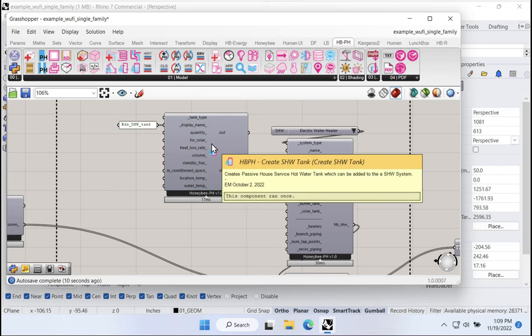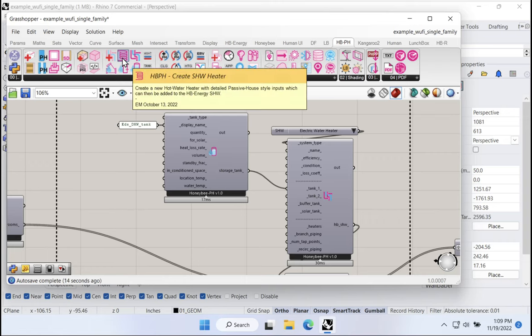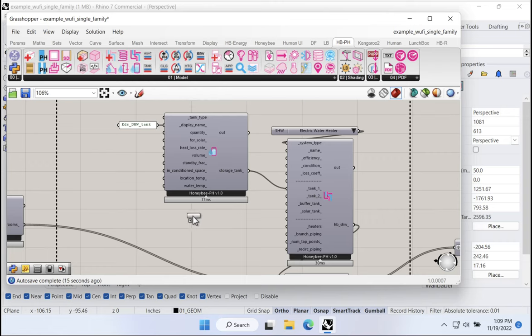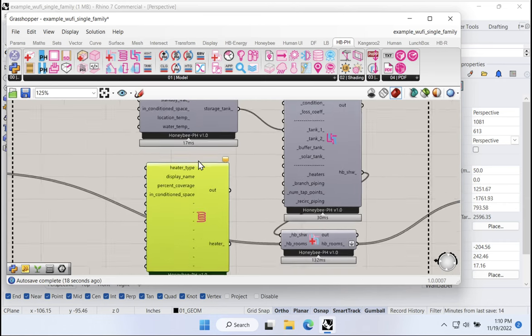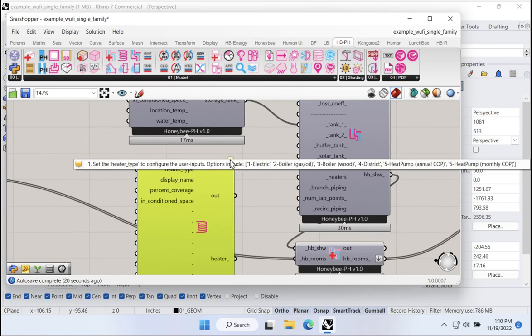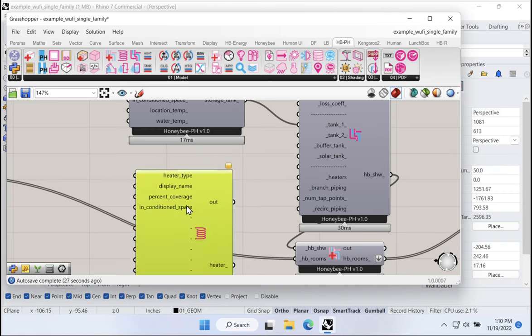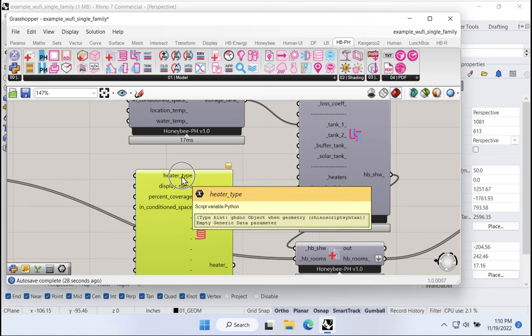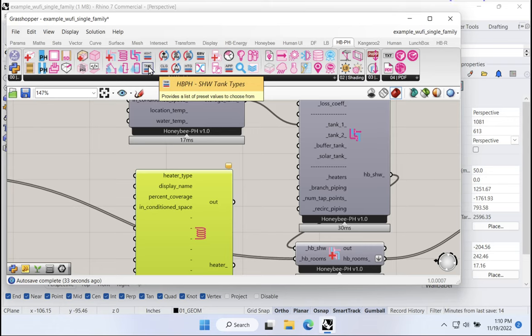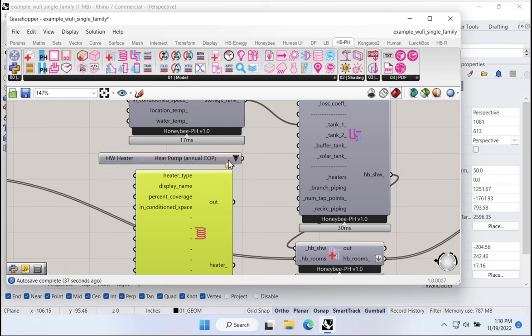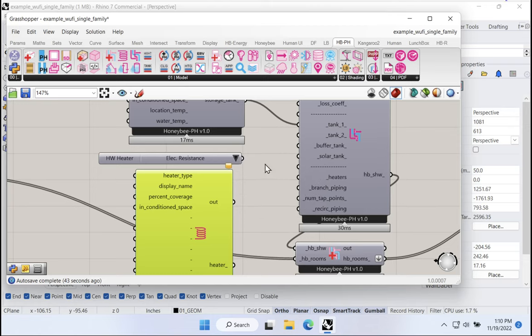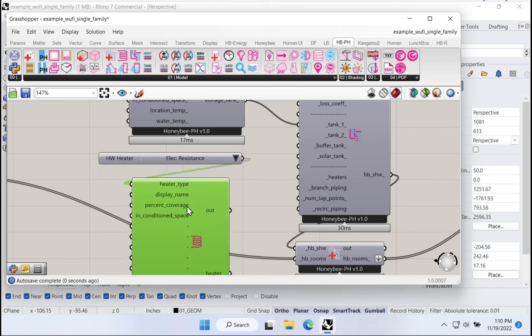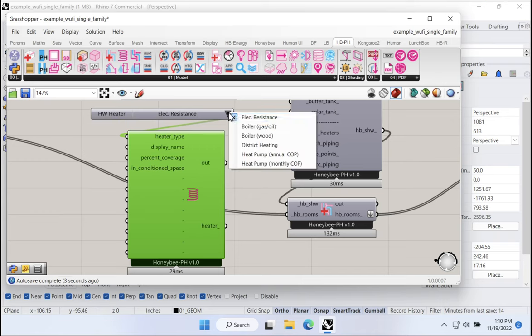Standby losses of four. Standby losses will be in watts per degree Kelvin. So that'll equate to about seven or eight BTUs per hour degree Fahrenheit or so. And a bunch of other parameters here. So we can obviously set up any of these parameters. Maybe we want to give this one a name. We'll call this Ed's domestic hot water tank. And we'll give that the display name there. That's really all we have to do to set up the tank. We can now take the tank and plug the tank in so we can add our tank to our system.